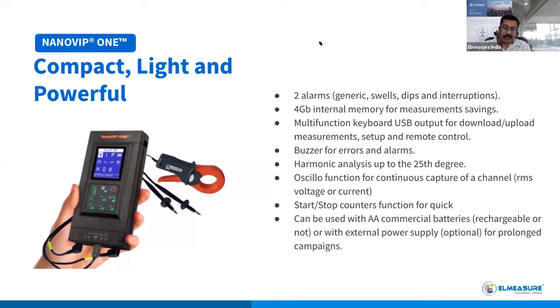Okay, and then harmonics, you can measure up to 25th degree. So this is again an important feature nowadays when you talk about power quality. I just want to go one step back now. The CEA guidelines of 2007, which got ratified in the year 2014, talk about the power quality, and the guideline says that the power quality meter should be there at the point of coupling, that is, we call it PCC, where you are going to have the meter connected to any of the customers.